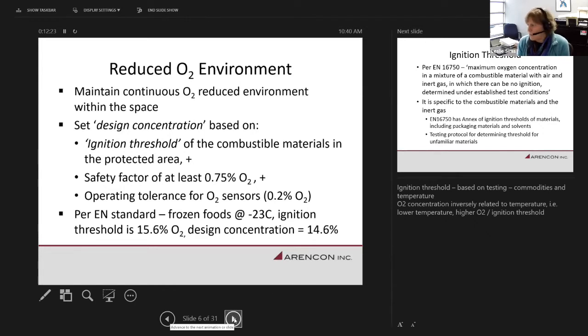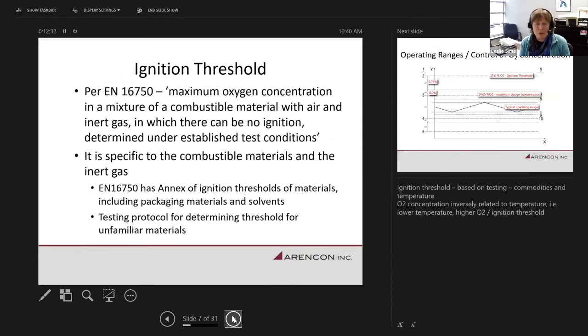Trying to think of what's next on here. So I want to go into the ignition threshold. The ignition threshold is a defined term. The standard that's referenced there, EN 16750, is a European norm. I'll go through the standards that are available dealing with oxygen reduction fire prevention systems. I'll come to a slide later where I've got a list of them, but this European norm is specific to oxygen reduction fire prevention systems, and it has to be through the use of nitrogen. So it's very specific. It's really been developed to address these systems.